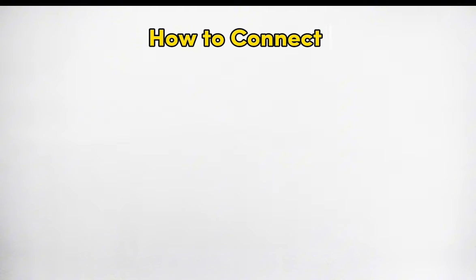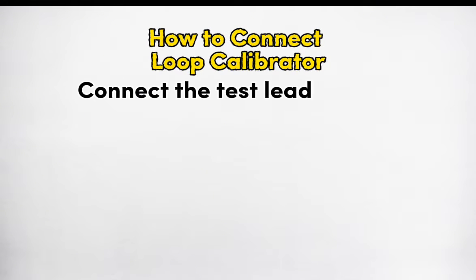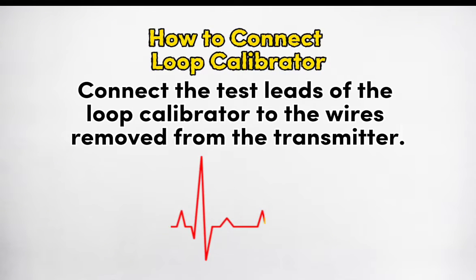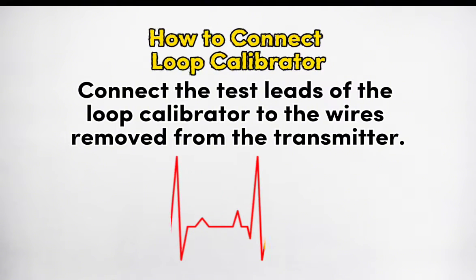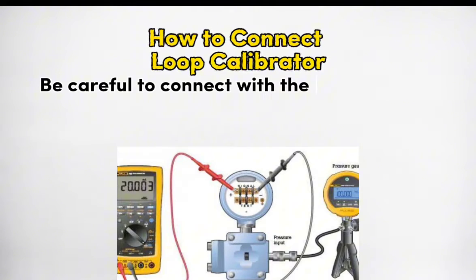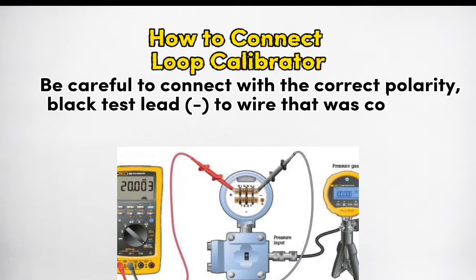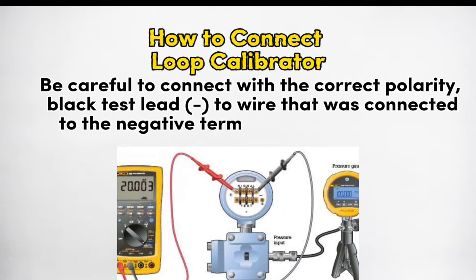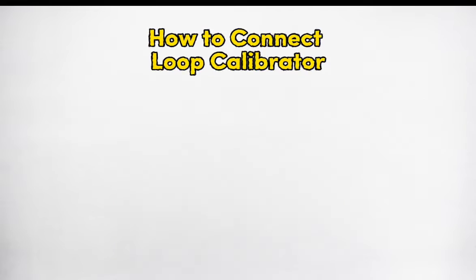How to connect the loop calibrator: connect the test leads of the loop calibrator to the wires removed from the transmitter. Be careful to connect with the correct polarity — black test lead to the wire that was connected to the negative terminal of the transmitter, red to the positive wire.